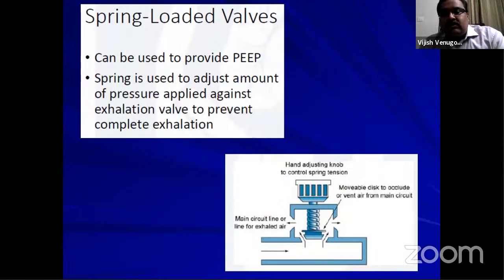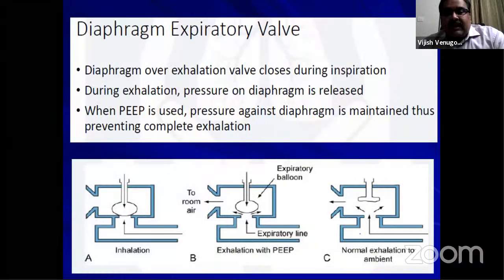It could be either spring-loaded valves. This is just like our APL valve. Then we have the diaphragm expiratory valve, as shown in the picture here. The diaphragm occludes during inhalation, and during exhalation, depending on the PEEP required, it will open the expiratory line to the atmosphere. If there is 0 PEEP here, as shown in C, it will be collapsed and all the air will come out.